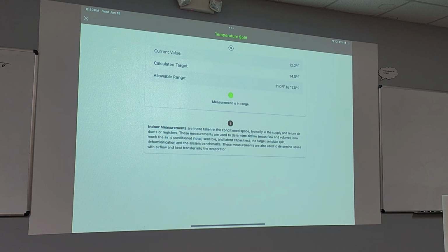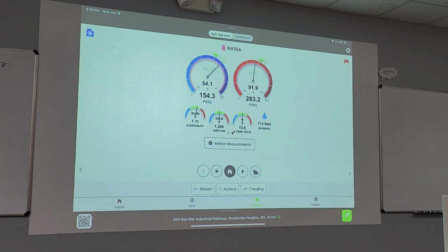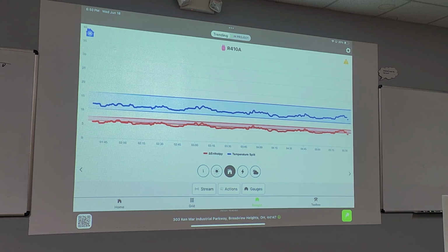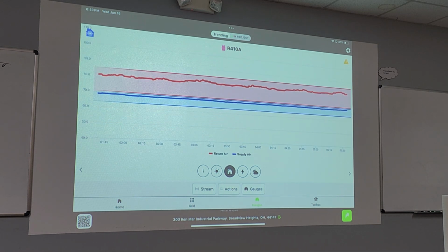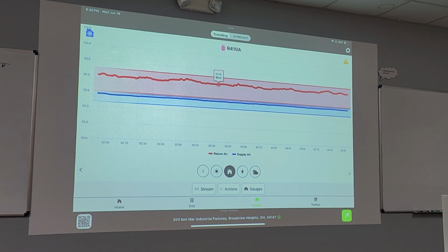Now the thing with this system is there's no ductwork on it. We just have the probes stuck to the bottom of it, so you have a ton of air recirculating underneath it, not to mention the door to outside wide open, so God only knows what the wind is doing. You could have this measurement, look at the gauge, or better yet, let's look at the trends. Our supply temp is pretty steady, but look at how the return temp is jumping all over the place.